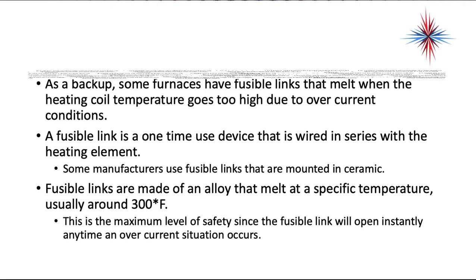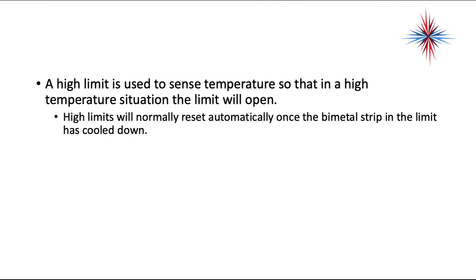As a backup, some furnaces have fusible links that melt when the heating coil temperature goes too high due to an overcurrent condition. A fusible link is a one-time device that is wired in series with the heating element. Some manufacturers use fusible links that are mounted in ceramic. Fusible links are made of an alloy that melts at a specific temperature, usually around 300 degrees. This is the maximum level of safety since a fusible link will open instantly anytime an overcurrent situation occurs.